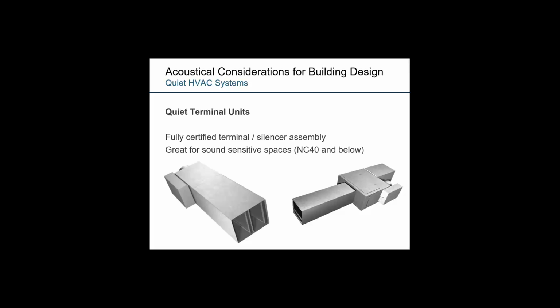Quiet terminal units are something that myself and a lot of my team members here at Price have spent a lot of time on, but something that essentially integrates two products together: a traditional VAV box and a noise control sound attenuator or silencer. The reason for it really is to create a quiet air moving device, taking a terminal unit and integrating a silencer into its design. And I mentioned here, it's great for sound sensitive spaces that might have low criteria that need to be achieved.